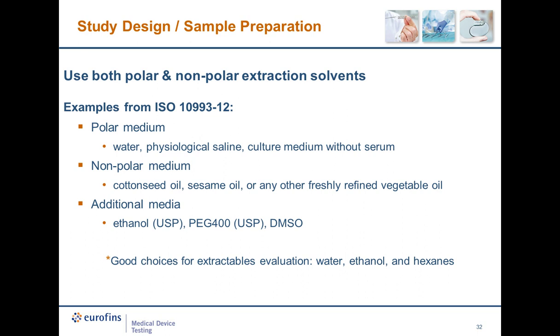Another consideration for the design of an extractables and leachable study is solvent choice. The standard recommends using both polar and nonpolar solvents. However, the examples provided in the current standard are not applicable to typical analytical methods used. For example, extracting in cottonseed oil is not appropriate for a GCMS or LCMS screening analysis. The Eurofins medical device team typically recommends water, ethanol, and hexanes to cover a variety of polarities. The proposed revision of Part 18 agrees with this recommendation. Again, it is important to note that solvents which compromise the integrity of the device should not be used. For example, if hexanes causes the device to swell during extraction, then it is not an appropriate extraction solvent.